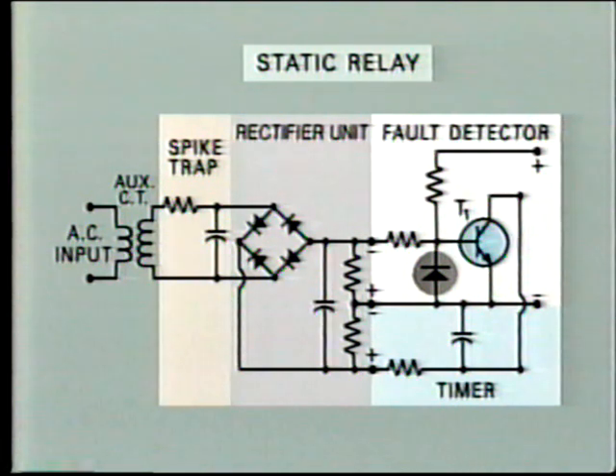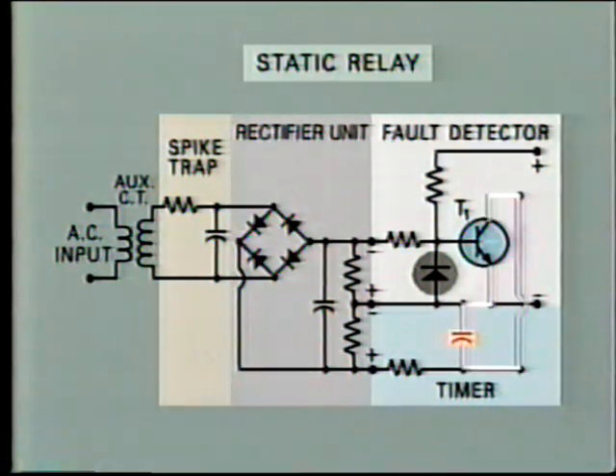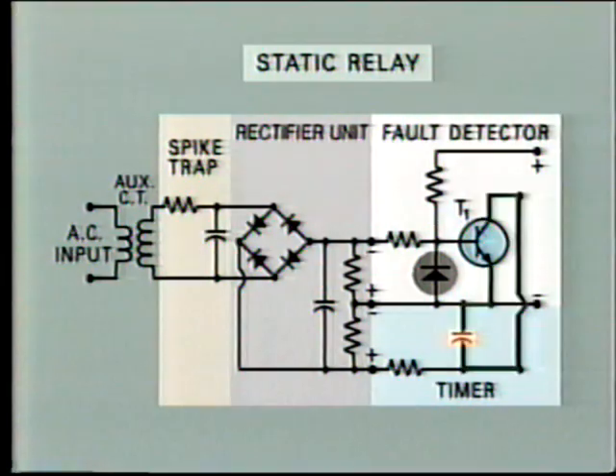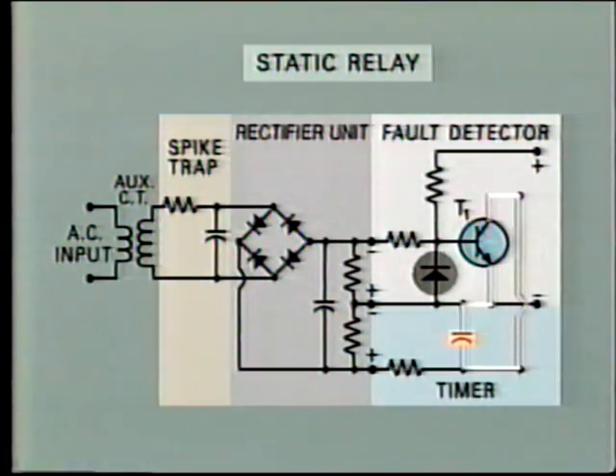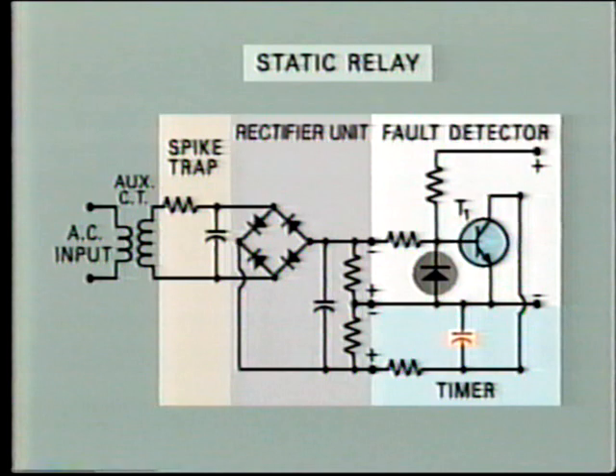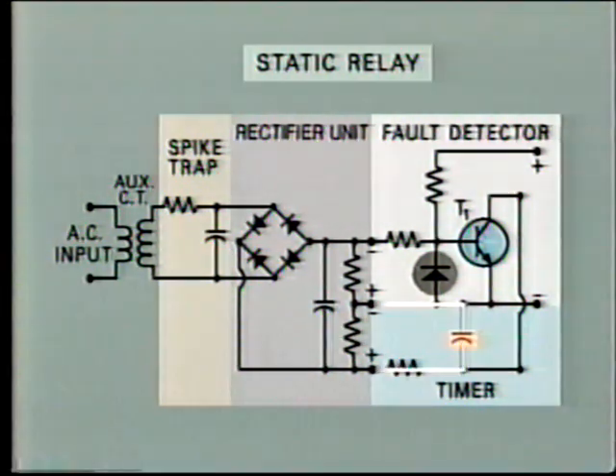As long as there is no fault, the timing circuit capacitor is short-circuited by the conducting transistor. Hence, the capacitor will not charge. However, as soon as a fault occurs, the short circuit is removed and the capacitor starts to charge, the time being dependent upon the magnitude of the current.